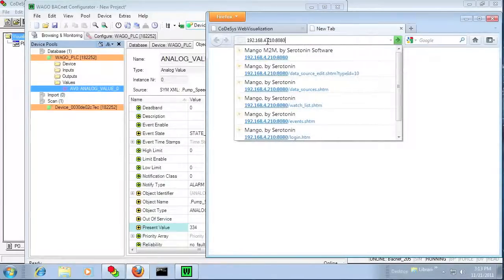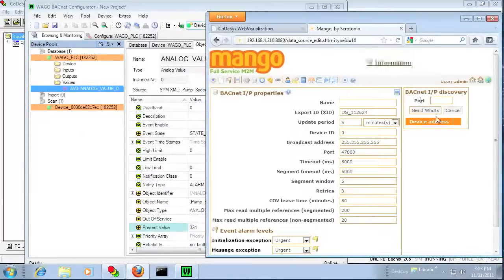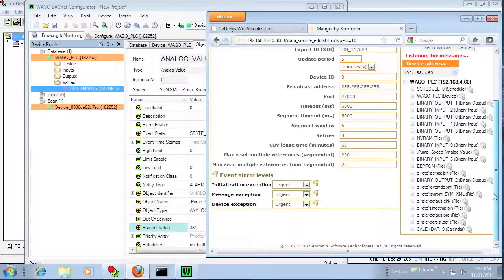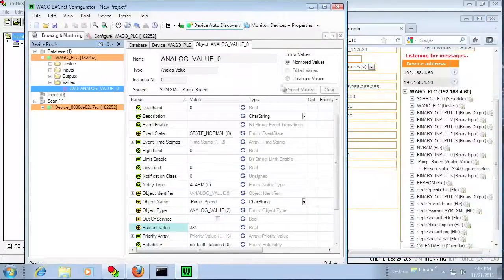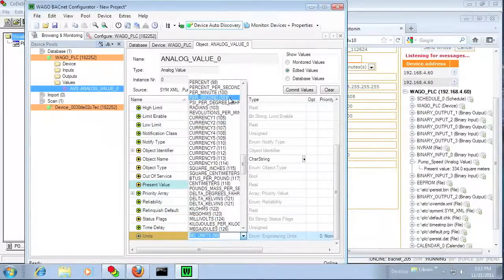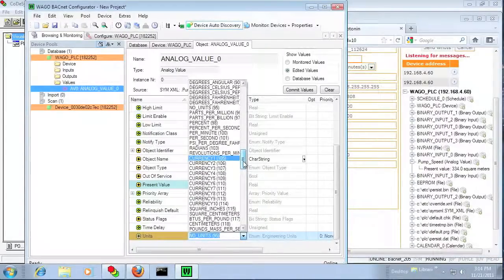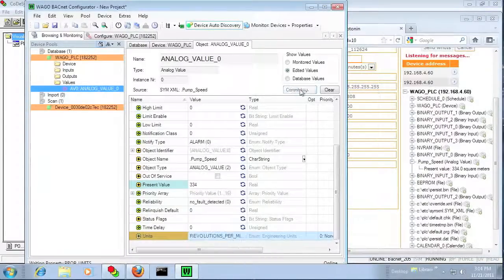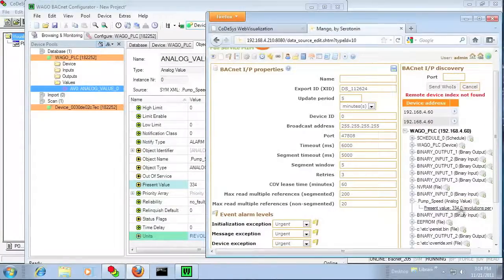What we have here is a BACnet client — it's open source software called Mango. Going into the who-is, it sees the PLC on the network. You can see all the values: the pump speed value we created, the internal variable, is updating from the PLC. Notice the units are wrong — I'm going to change that to RPM, since square meters doesn't really fit pump speed. I'll commit those values, and you can see how that updates the clients automatically. That's the nice thing about BACnet — because it's object-based, all clients get updated with all the parameters.